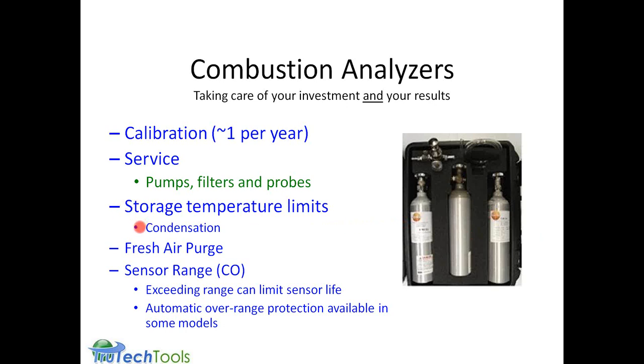Storage temperature limits, you want to be careful because we talked about water vapor that's inside the flue gas, and that the flue gas makes its way throughout the meter, and that water can condense. And when water condenses, if it freezes, if it gets below the freezing point, it can cause mechanical damage due to ice buildup. So you just want to be sure that you empty your condensate trap, and you do not store it in sub-freezing temperatures. The testo meters do have very good protection against that. Some very good membranes cover the sensors to keep water from getting in, but I still wouldn't mess with it. If you can take it in on a cold night, you should take it in.